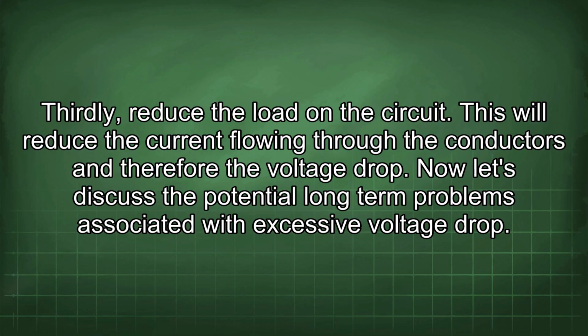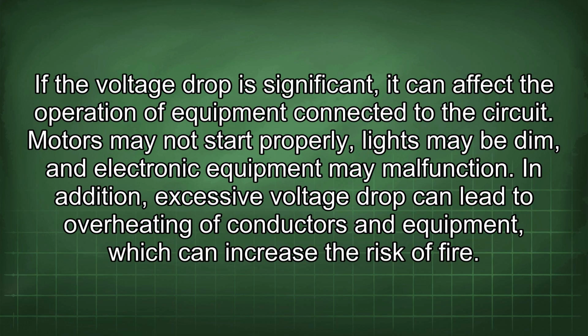Now let's discuss the potential long-term problems associated with excessive voltage drop. If the voltage drop is significant, it can affect the operation of equipment connected to the circuit. Motors may not start properly, lights may be dim, and electronic equipment may malfunction. In addition, excessive voltage drop can lead to overheating of conductors and equipment, which can increase the risk of fire.